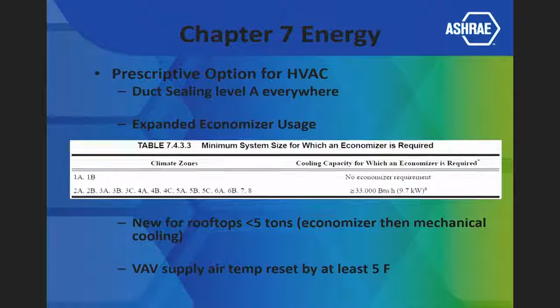In the dead of winter, remember, part of the reason I'm driving that temperature down at the unit is to take moisture out of the air and dehumidify the air. In January and February, we've got buildings that have low humidity. So why are we taking all the moisture out of the air? Let's set the temperature up a little bit. So this has to do with what's called supply air reset.